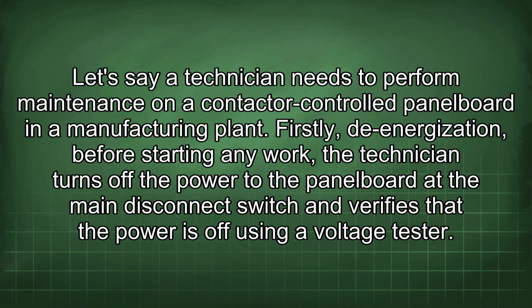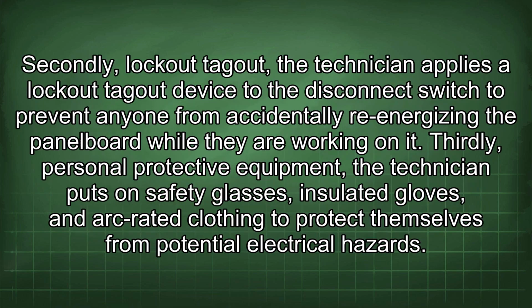Let's say a technician needs to perform maintenance on a contactor-controlled panel board in a manufacturing plant. Firstly, de-energization. Before starting any work, the technician turns off the power to the panel board at the main disconnect switch and verifies that the power is off using a voltage tester. Secondly, lockout-tagout. The technician applies a lockout-tagout device to the disconnect switch to prevent anyone from accidentally re-energizing the panel board while they are working on it.